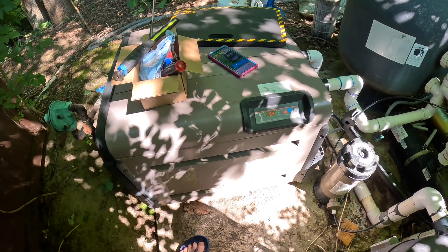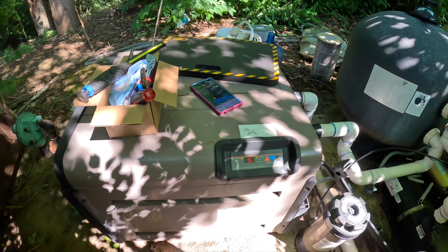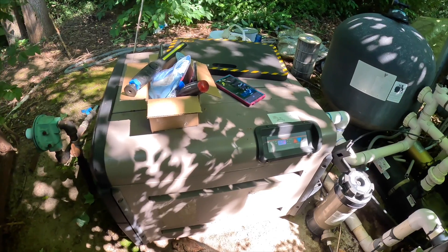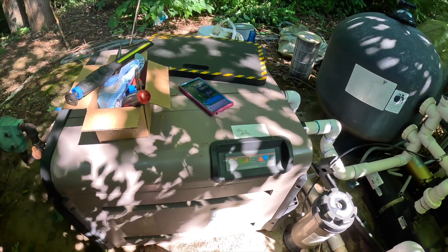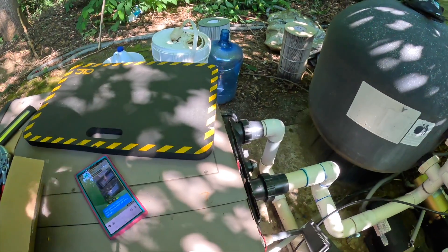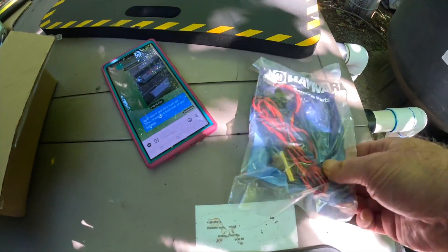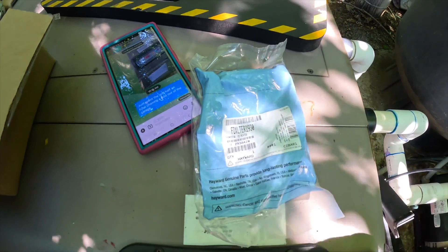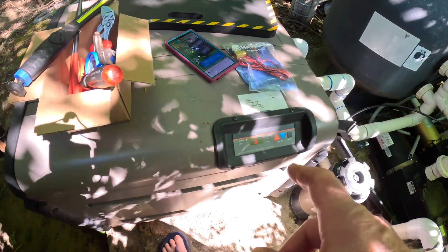Here's where we are with the Hayward pool heater. See that code 'SF' — Service. What happened was we had torrential rain, the heater was fine, then we got that code. I did some research and it turns out it's this part right here — the thermistor or thermostat, part number FDXLTER1930. This is a 400,000 BTU propane heater. It's just four Phillips screws — in my case three because one is missing.